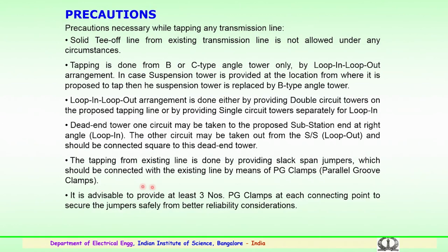The tapping from the existing line is generally done by providing slack span jumpers. Jumper conductors of the actual rating of the conductor are provided for the tapping of the existing transmission lines, which should be connected with the existing lines by means of parallel groove clamps. These are PG clamps, as they are known by the utility engineers, and these have to be employed. It is also advisable to provide at least 3 parallel groove clamps at each connecting point to secure the jumpers safely, from better reliability considerations.